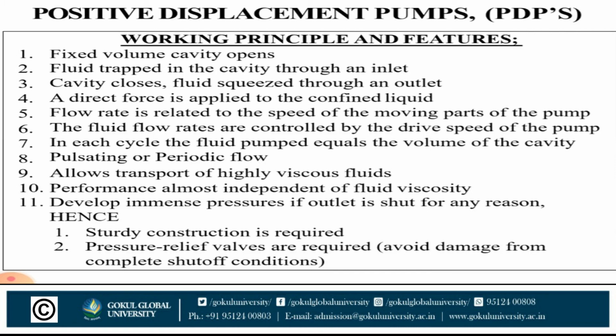Positive displacement pump working principle: a fixed volume cavity opens, fluid is trapped in the cavity through an inlet, the cavity closes, and the fluid is squeezed out through an outlet. A direct force is applied to the confined liquid. Fifth, flow rate is related to the speed of the moving parts of the pump. The fluid flow rate is controlled by the drive speed of the pump. Seventh, in each cycle, the pump delivers fluid equal to the volume of the cavity.